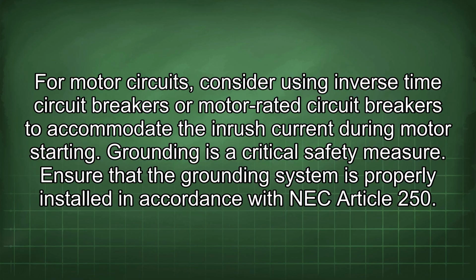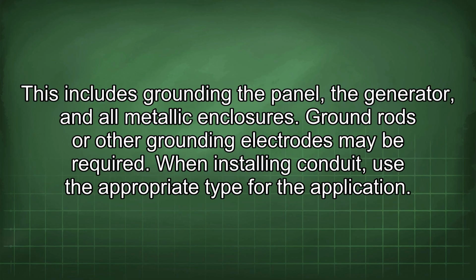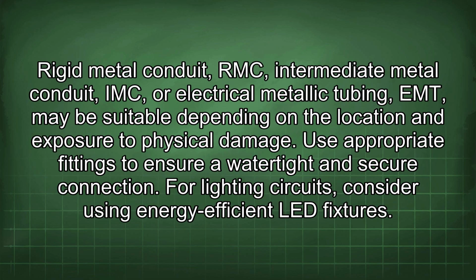Ensure that the grounding system is properly installed in accordance with NEC Article 250. This includes grounding the panel, the generator, and all metallic enclosures. Ground rods or other grounding electrodes may be required. When installing conduit, use the appropriate type for the application. Rigid metal conduit, RMC, intermediate metal conduit, IMC, or electrical metallic tubing, EMT, may be suitable depending on the location and exposure to physical damage. Use appropriate fittings to ensure a watertight and secure connection.